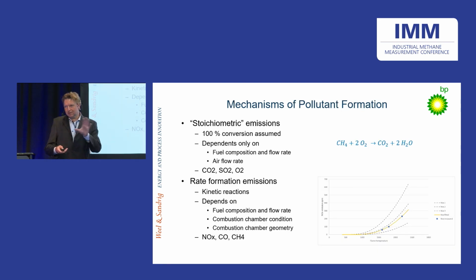We basically have two kinds of emissions. The simple emissions are what we call stoichiometric emissions, which we can calculate based on the flow rates and composition of the fuel, and the airflow rate. For instance, if you have sulfur content in your fuel, all that sulfur will basically end up as SO2 in the stack. That's the simplest thing to implement in a PEMS model.